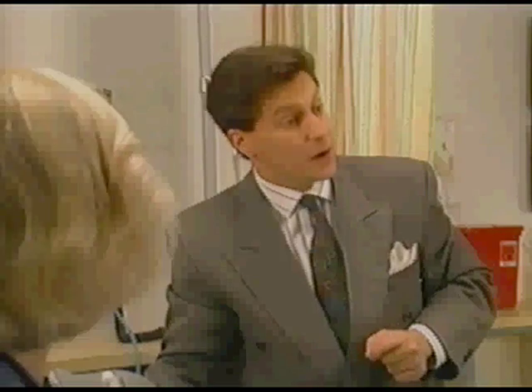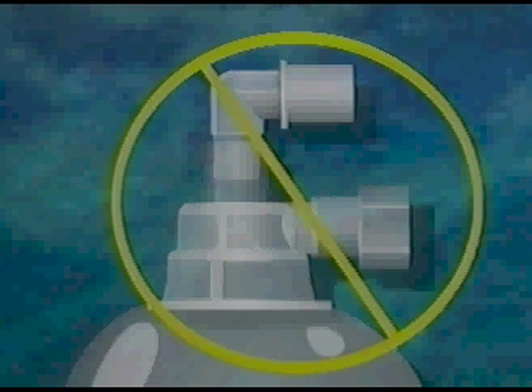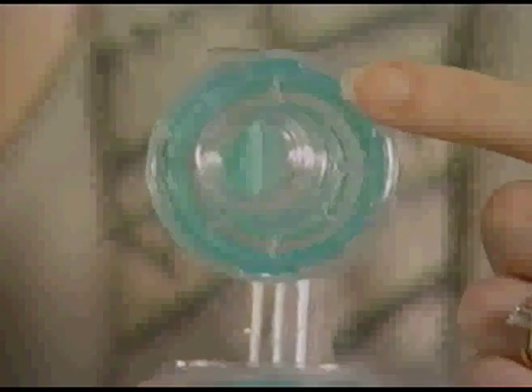What happens if the patient vomits? That's a very important consideration. BagEasy is designed to keep vomitus in a small contained area. The patented design of the duckbill valve incorporates a ring which blocks the vomitus from moving past it. Additionally, the valve is located near the patient connector, so there's no long tube or elbow to get clogged. A good squeeze generally clears the bag, and with a quick rinse you're back in service. Another good feature is the exhalation port on the patient valve, which directs the patient's exhalations back toward the patient and away from the caregiver.